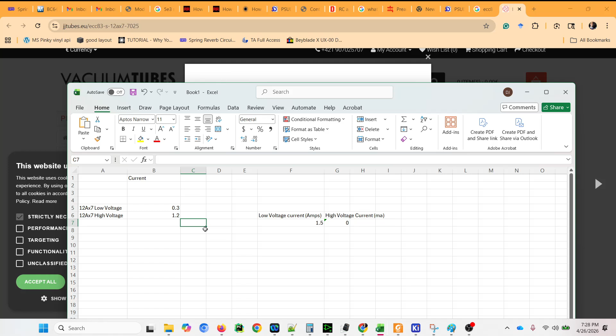Now how about the high voltage? The data sheet will also tell you what voltage you need and how much current you're going to be asking from your power transformer. It's telling you that it's typically going to pull about 1.2 milliamps from the plate — A stands for anode, another word for the plate. So our high voltage winding is going to need 1.2 milliamps. Let me get rid of this formula real quick.